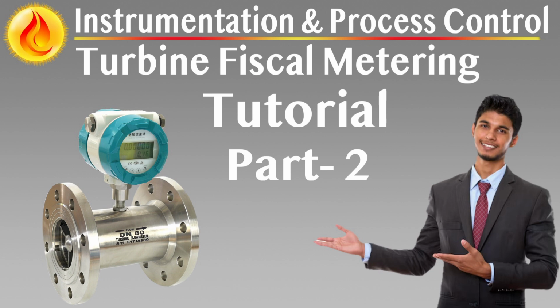Air supply for pneumatic actuators. Where flow control or valve actuation is pneumatically operated, instrument air must be provided to the skid. The air supply must be clean, dry, and oil-free, as contamination will degrade actuator performance and increase failure risk. The air pressure specification must be clearly defined in the requisition. Connections must terminate in half-inch NPT female threads, and all pneumatic tubing and fittings must be constructed from AISI 316L stainless steel. For sour service environments, materials such as Monel or Hastelloy C may be specified. Copper tubing is explicitly prohibited due to corrosion and safety risks.